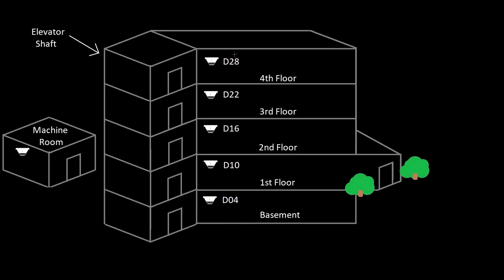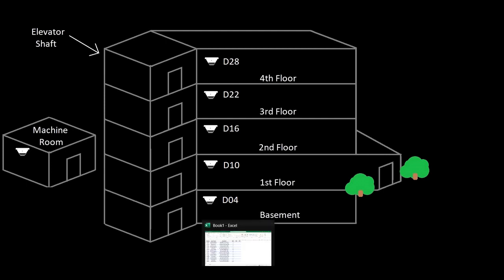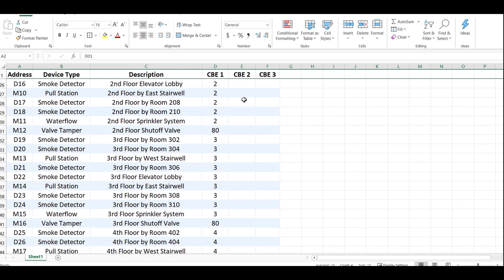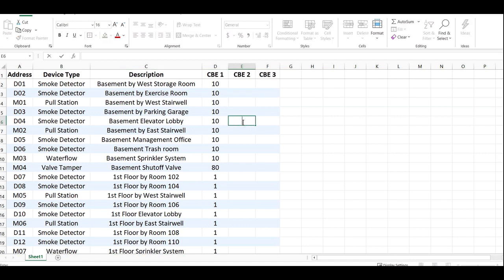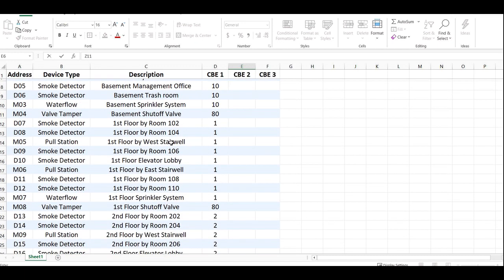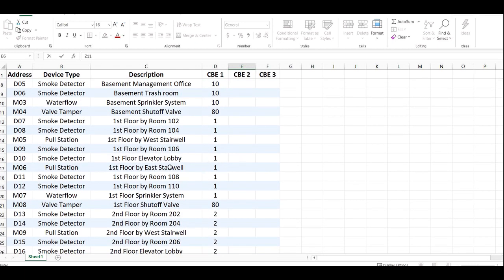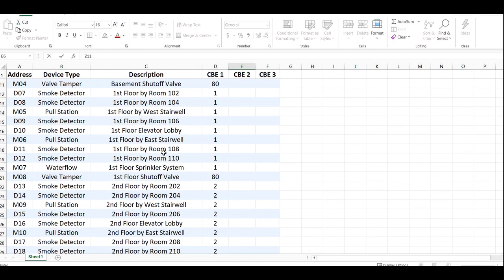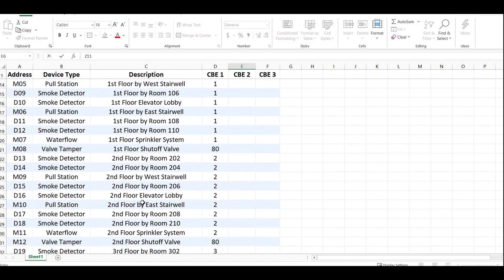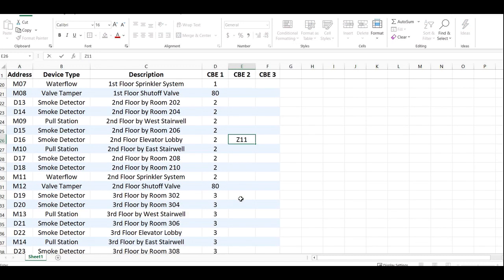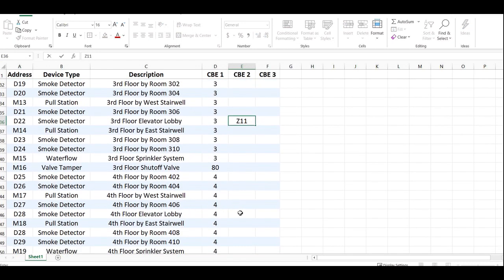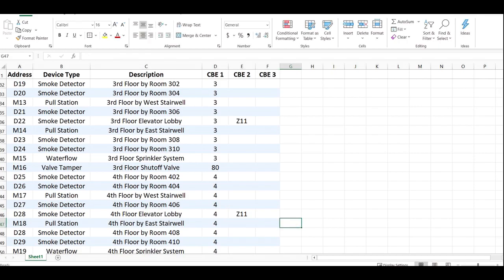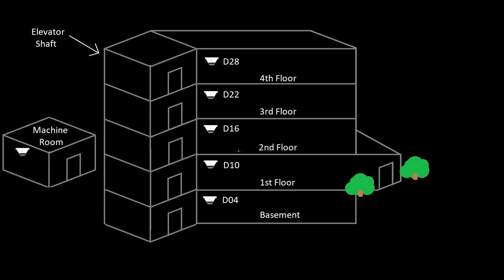If an inspector tells you something like that then so be it, but in our example we're just using the elevator lobby. What I'm going to do is I'm going to go and group all of the detectors that I want to bring the car down to the first floor into their own unique group. On the type of panel, let's say this is a Fire-Lite, we're just going to add another zone to it. The elevator lobby, we can still have it trigger zone 10, whatever zone 10 is doing, maybe that's for strobes or something, but then let's also make it do zone 11 for primary. We're going to skip the first floor for right now because we don't want the first floor smoke to send it to the first floor. Then the second floor elevator lobby is right here, we'll make this zone 11. Third floor elevator lobby, that's zone 11. Fourth floor elevator lobby, zone 11.